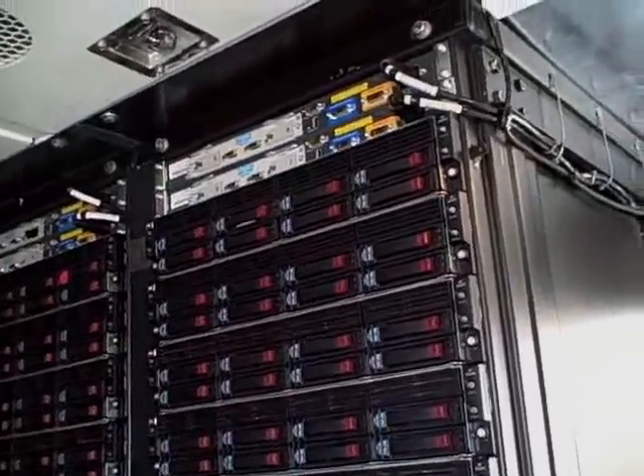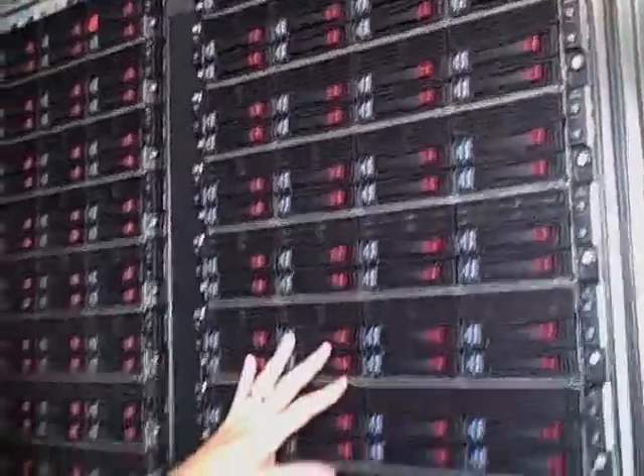The racks aren't your traditional standard 7-foot rack — they're slightly taller. They are 50U tall, and the reasons for that: one, we had a bit more space so we wanted to use the capacity. Second, it allows us to anchor them top and bottom. These are specially stronger racks, designed to transport the IT inside the container. So when we ship to a customer, if they want us to, we'll ship all the IT already deployed in the container and they get it ready to switch on.